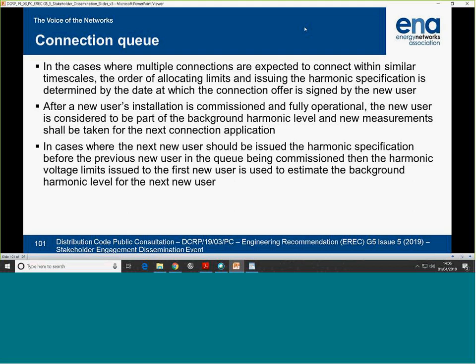So the way we do capacity at the moment is the same thing. As I say, 2 offers go out that are based on megawatt capacity existing in a certain area, and they're both after that same capacity, they become interactive with each other. If we were in a world where harmonic studies were done during the offer period, which we're not, but okay, let's assume you're in that world where you could do it, then almost every offer in a certain area, I would presume, would probably go interactive with each other.